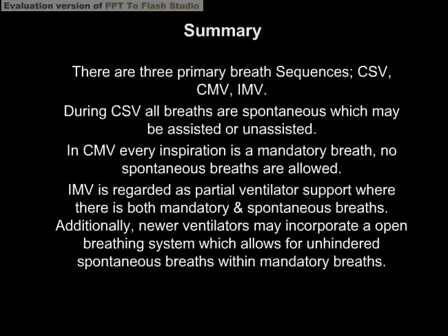In summation, there are three primary breath sequences: CSV, CMV, and IMV. During CSV, all breaths are spontaneous, which may be assisted or unassisted — pressure support is an example of an assisted spontaneous breath. In CMV, every inspiration is a mandatory breath; no spontaneous breaths are allowed, though spontaneous efforts are followed by a fixed pressure or volume for a set amount of time. IMV is regarded as partial ventilatory support, with both mandatory and spontaneous breaths. Additionally, newer ventilators may incorporate an open breathing system, which allows for unhindered spontaneous breaths within mandatory breaths.